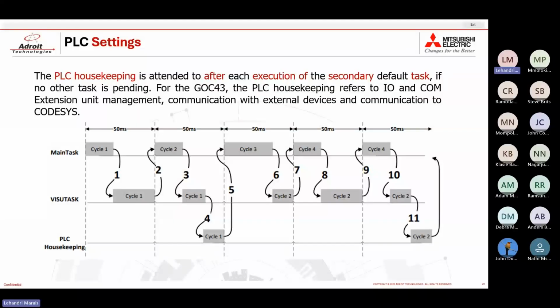So if the main task is not pending to run, your PLC housekeeping will be attended to. The PLC housekeeping for the GOC43 mainly refers to I/O and COM extension unit management, as well as communication with external devices and communication to a PC that is running CODESYS.